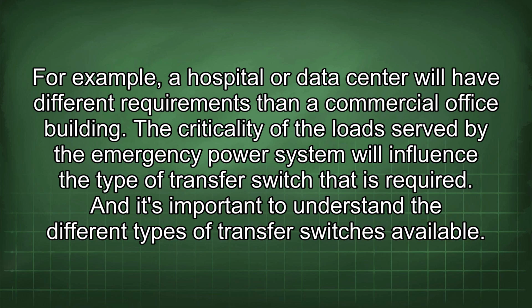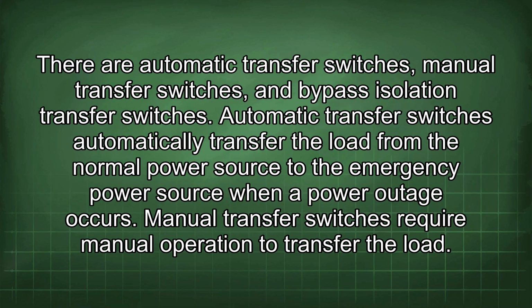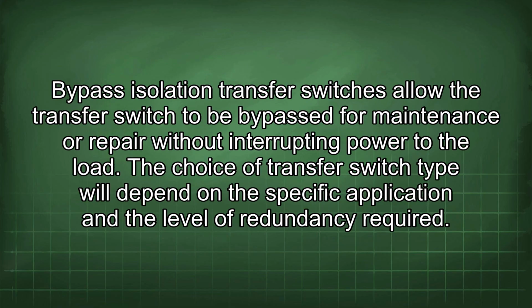And it's important to understand the different types of transfer switches available. There are automatic transfer switches, manual transfer switches, and bypass isolation transfer switches. Automatic transfer switches automatically transfer the load from the normal power source to the emergency power source when a power outage occurs. Manual transfer switches require manual operation to transfer the load. Bypass isolation transfer switches allow the transfer switch to be bypassed for maintenance or repair without interrupting power to the load.